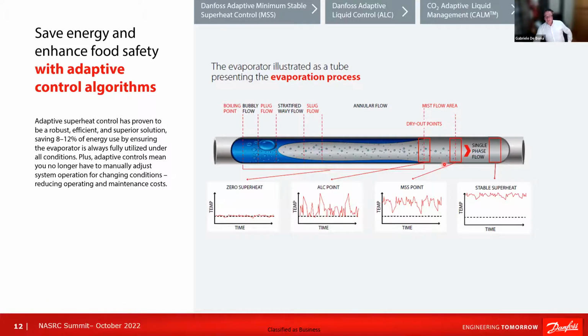The cabinet has been filled with fresh product, or is empty because the selling of the product has been very high for that day. So this value is changing. The MSS algorithm, minimum stable superheat, is able to detect this change and automatically adapt to the new condition. A further development of this algorithm is the ALC, adaptive liquid control, that, working in combination with the liquid ejector, can take the most out of the evaporator and allow the evaporator to be used to the fullest.